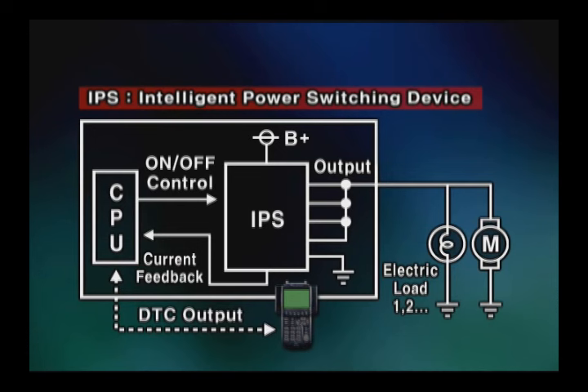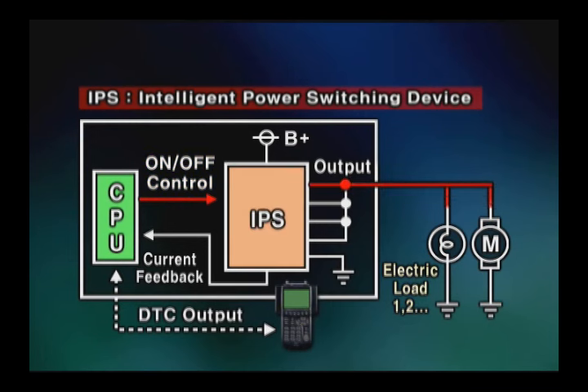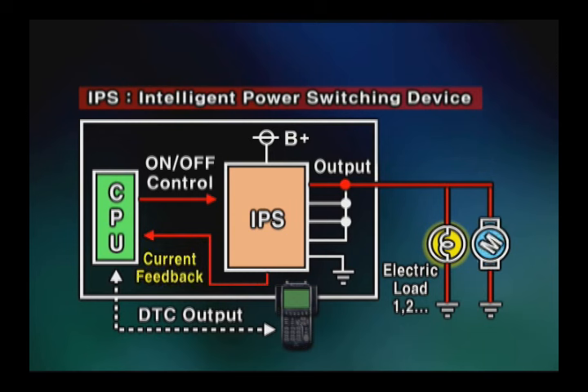As the CPU sends the on-off operation signal of motor or lamp to the IPS, the IPS outputs the electric power for operating the electric load. At the same time, the IPS detects the current flowing through the output terminal and feeds it back to the CPU.